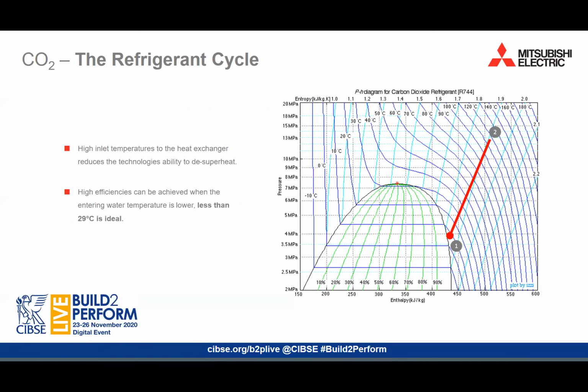At point 2, this is when the refrigerant enters into the gas cooler. As an example, if the water inlet temperature to the gas cooler is 60 degrees, then the ability to desuperheat the discharge gas is significantly reduced. Here we see that the gas can only cool to a temperature of approximately 60 degrees. And this means that the delivered enthalpy through the heat exchange cycle between points 2 and 3 is only approximately 120 kilojoules per kilogram. At point 3, the refrigerant enters into the expansion valve where the pressure and temperature are both reduced before entering the evaporator at point 4.